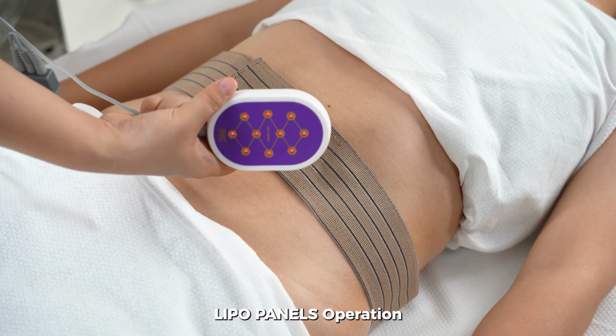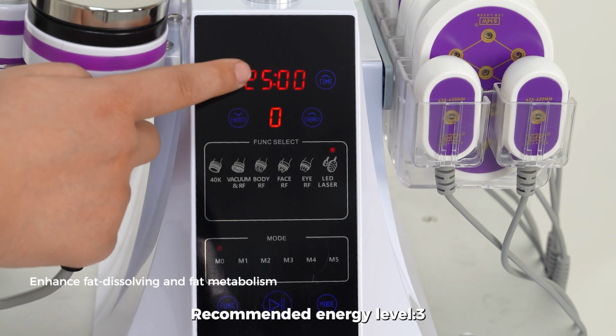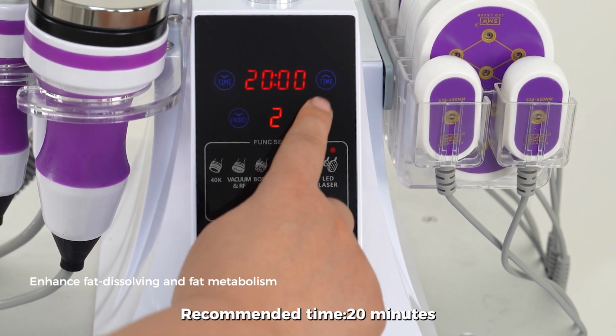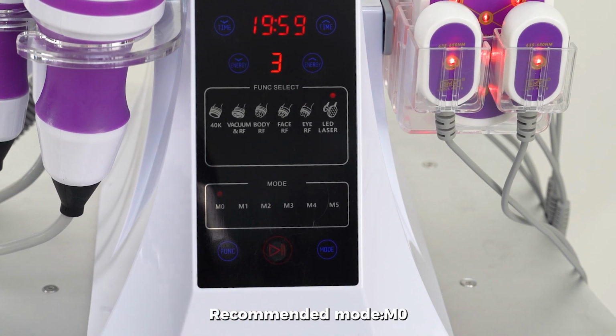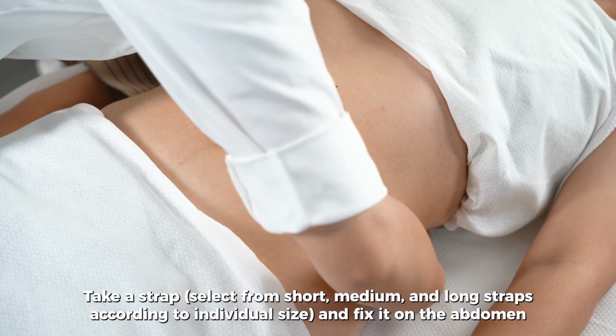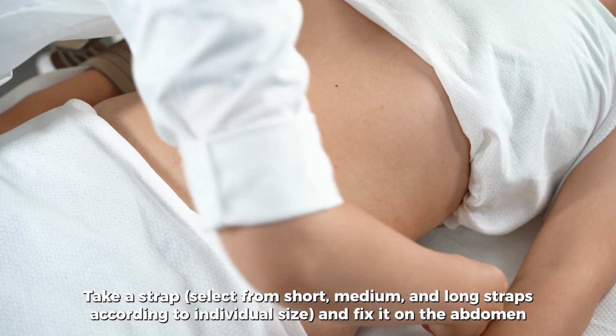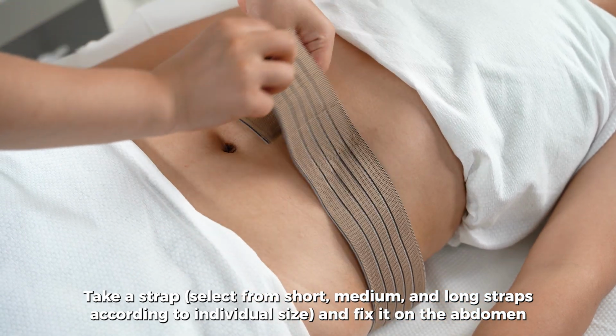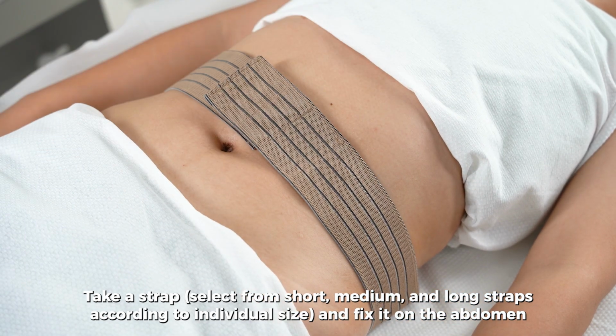Lipo panels operation. Recommended time, 20 minutes. Recommended energy level, 3. Recommended mode, M0. Take a strap, select from short, medium, and long straps according to individual size, and fix it on the abdomen.